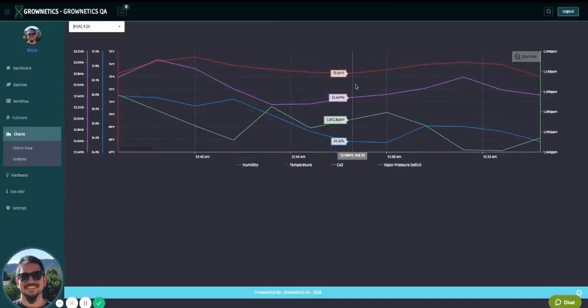This is incredibly useful when doing long date ranges and you want to focus on a week or a day and get down to the minute. We're logging about every 10 seconds on average for every sensor in the facility, so we're collecting an incredible amount of data, which has proven really valuable for our clients for alerting, zone monitoring, troubleshooting, and optimizing airflow models and environmental controls for their zones.